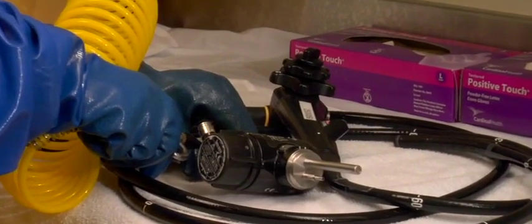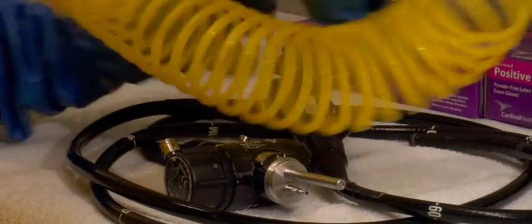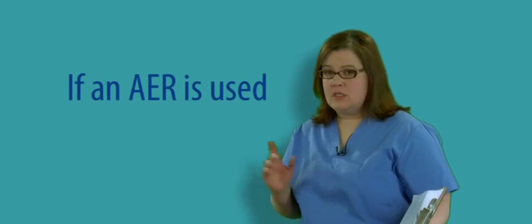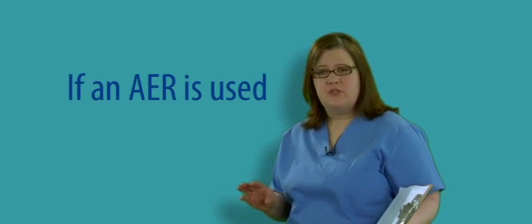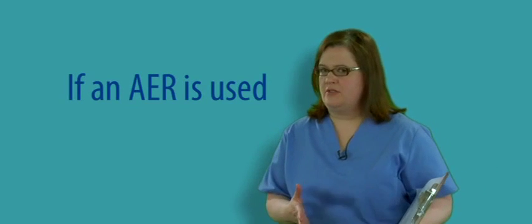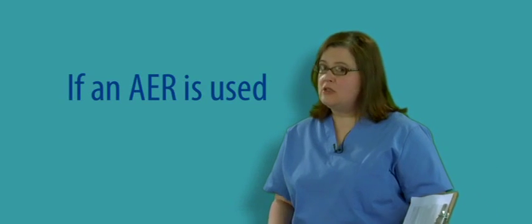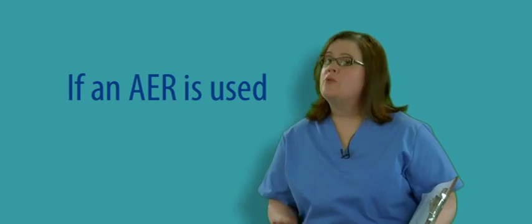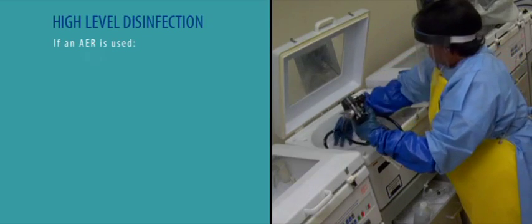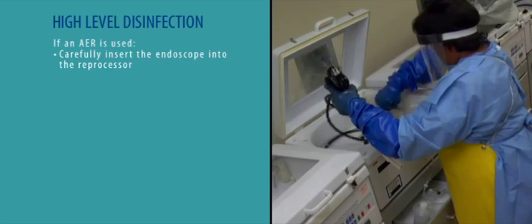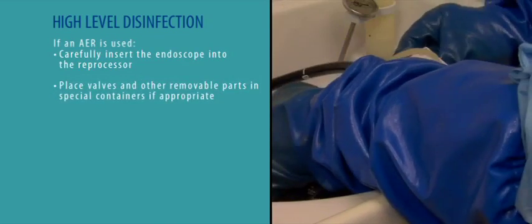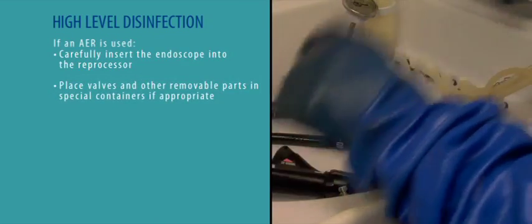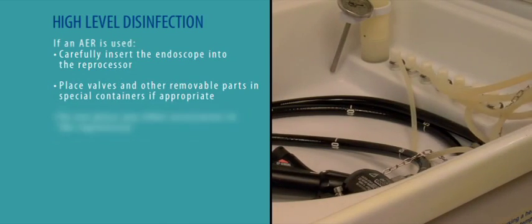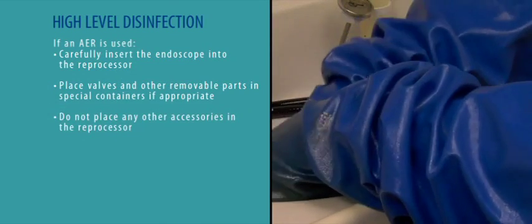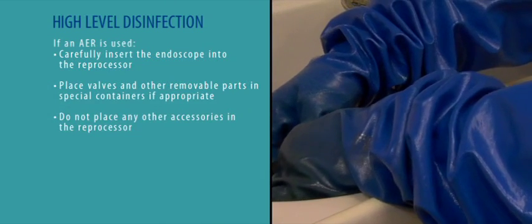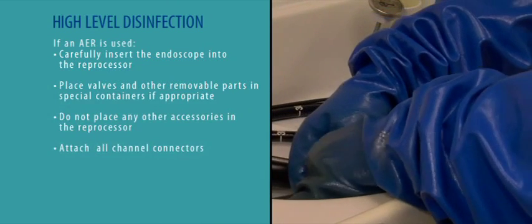When the soak is completed, purge all channels with air to remove disinfectant. If an AER is used, consult the manufacturer's guidelines for the procedure to connect the endoscope to the reprocessor. Follow all steps for the mechanical cleaning and rinsing of the endoscope prior to disinfection. Carefully insert the endoscope into the reprocessor. Place valves and other removable parts in the reprocessor in special containers, if appropriate. In order to prevent damage to the scope, do not place any other accessories in the reprocessor. Attach all channel connectors.